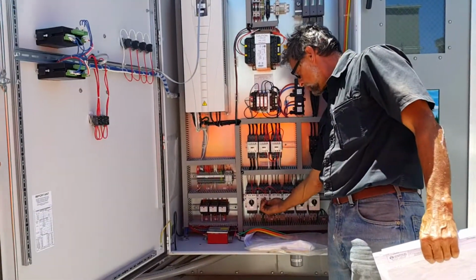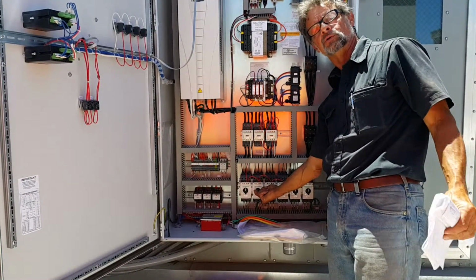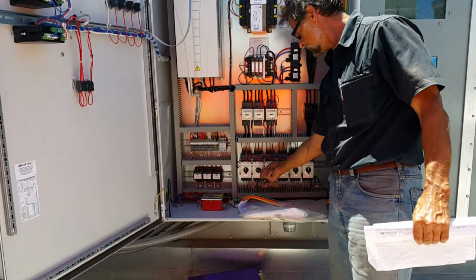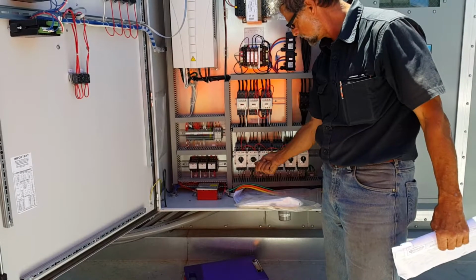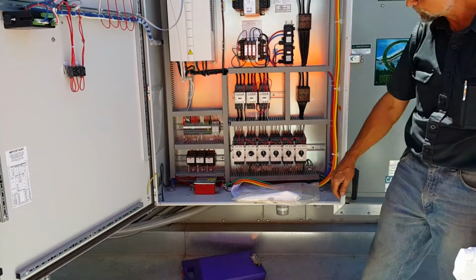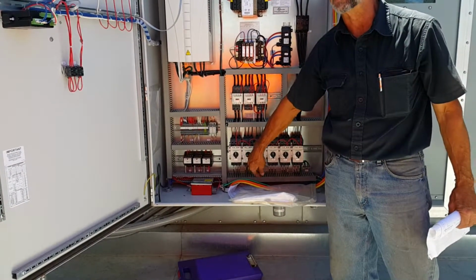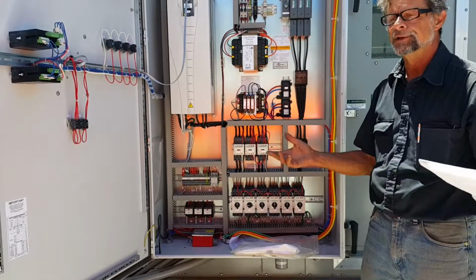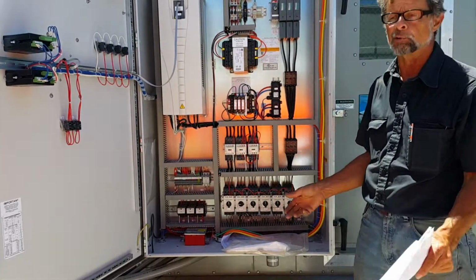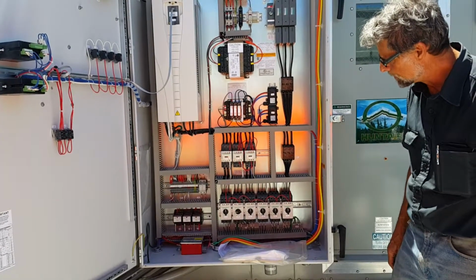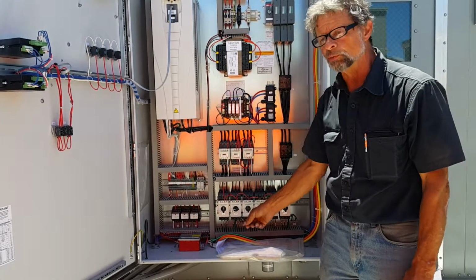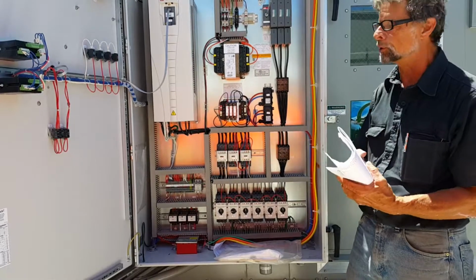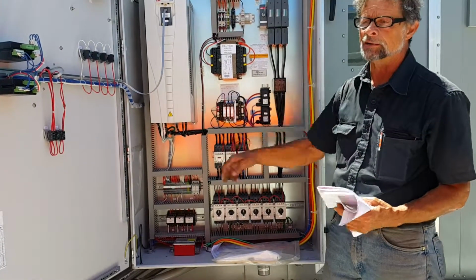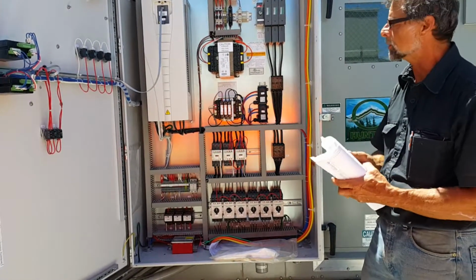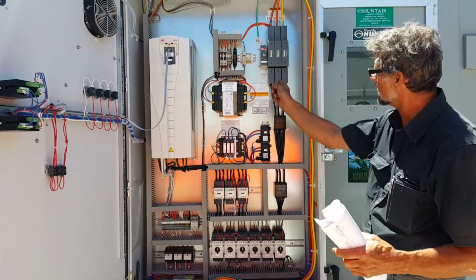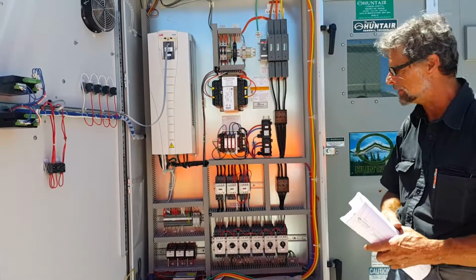If it trips, you're going to see a middle position like you do in a regular circuit breaker trip. You see that, the motor's been tripped. That's the off position. So in the trip position, you want to take a look at the motor, see if it overamped, or did it blow up, did it go to ground. If something happens to one of these motors very violently and it causes enough current, you're going to take the drive down, go off on current limit, or you might take a fuse out somewhere here, or something that would cause it to go down.